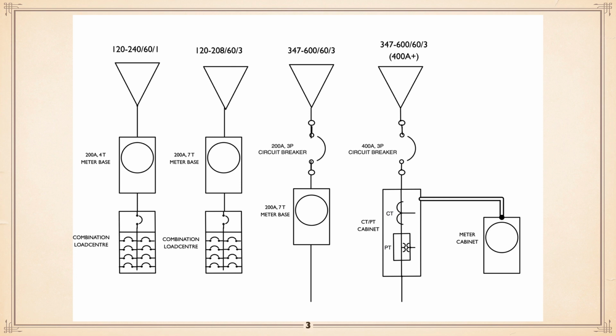Now, to give you an idea, this is how they're drawn. And if you know how these are drawn, then you can look at it and see what the message is that's trying to come across. Basically, the triangle will be incoming power, and above it, the power supply that is intended from the utility. Start with the beginning, 120/240 single phase, typical household meter base, and then to a combination load center.